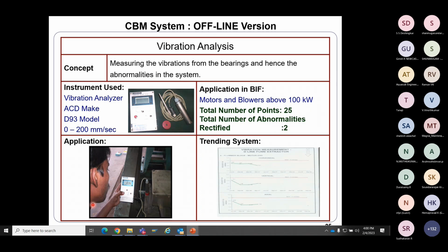As I was telling you earlier, these vibrations can happen because the balancing is not proper, because a foundation bolt has loosened, because of some crack in the foundation itself, because of some bearing failures or whatsoever. So when you measure this periodically, and you find either the displacement or the velocity going out of range, obviously something is going wrong.